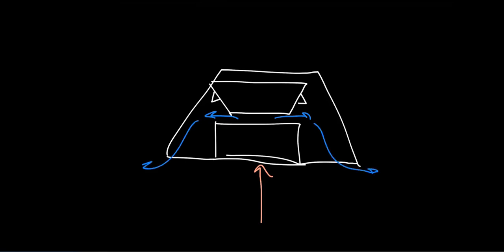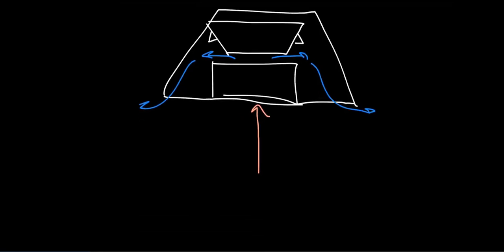The induced room air mixes with the primary air jets and is pushed into the room via supply air slots. The important thing to note is that an active chill beam not only functions as a cooling and heating terminal unit, but also serves as an air diffuser and should be selected as such, giving due consideration to thermal comfort and throw direction.